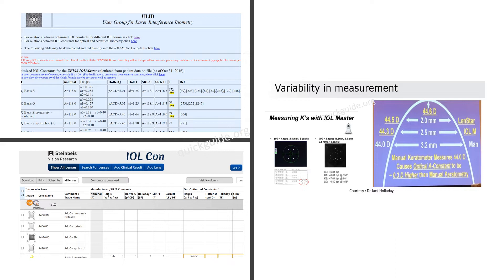To understand this, let us take a step back in history. When the optical biometry IOL Master was first launched, it started measuring 2.5 mm of the cornea. Prior to that, keratometry was more often done with manual keratometry, which measured at 3.2 mm. With two-variable formulas like Holladay 1, SRK/T, and similar formulas available at that time, they were all optimized on the basis of manual keratometry.